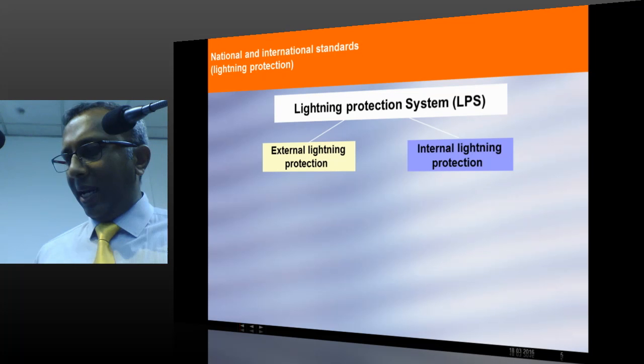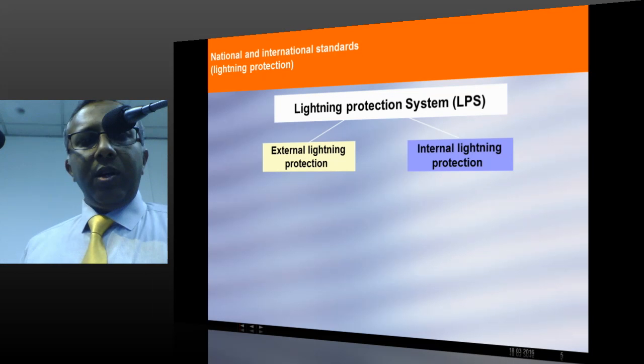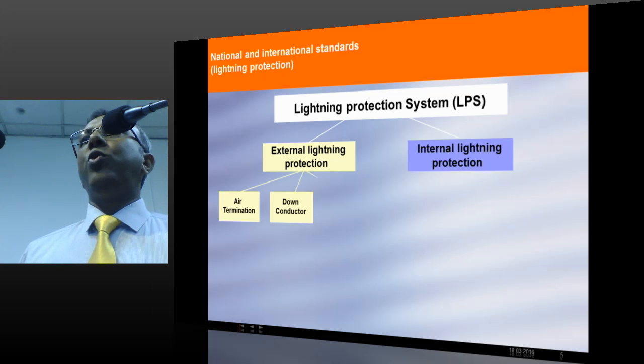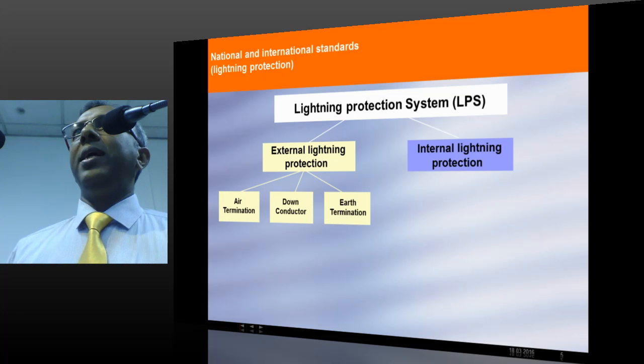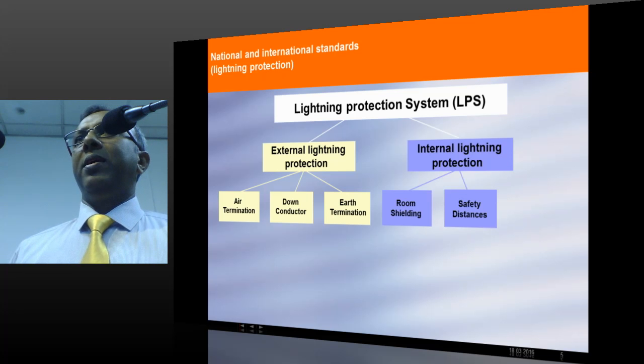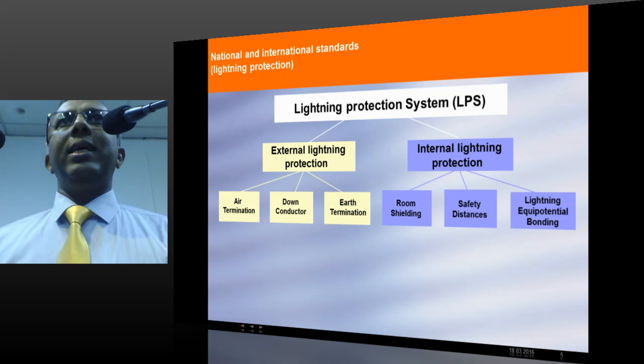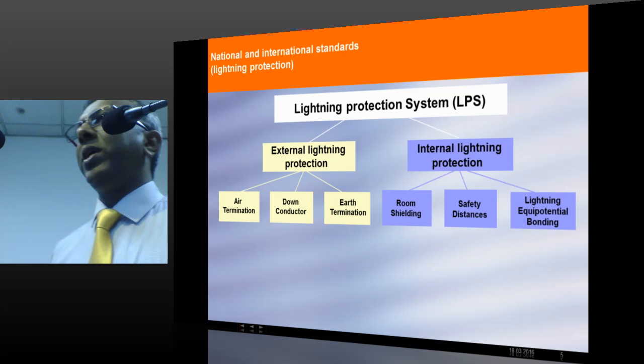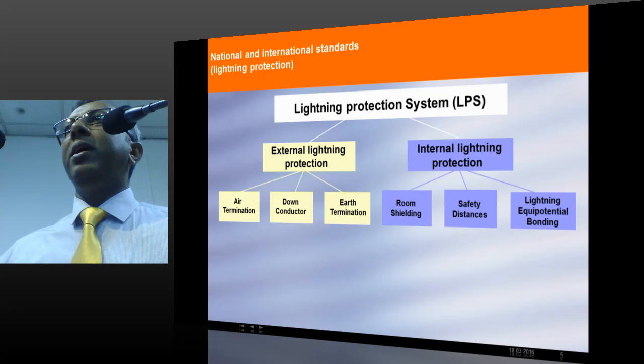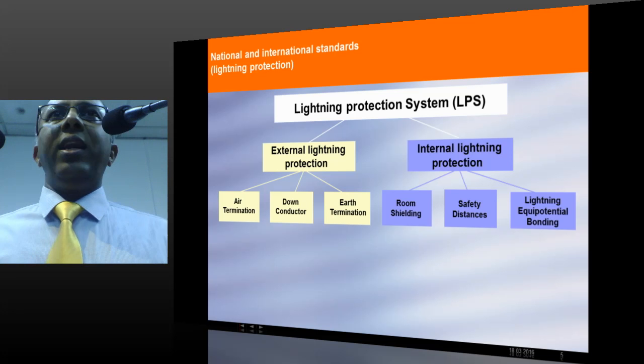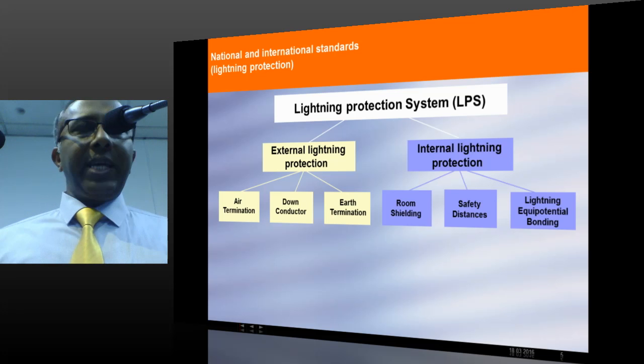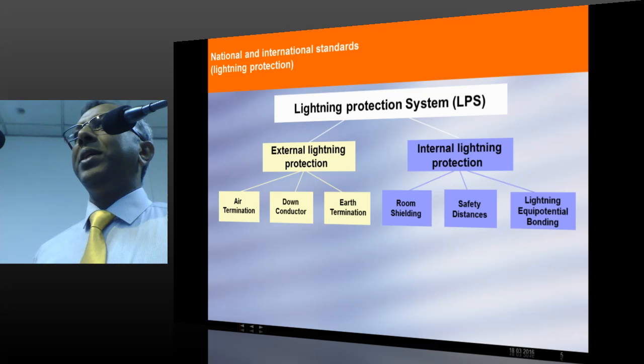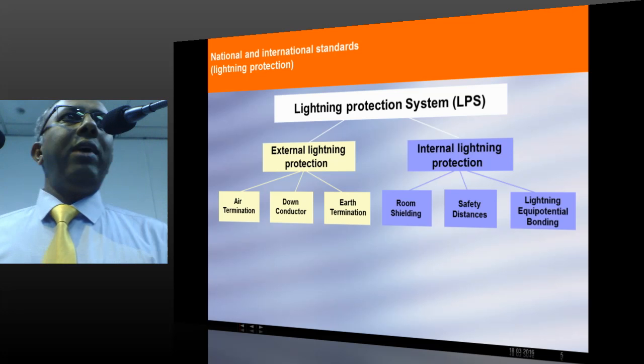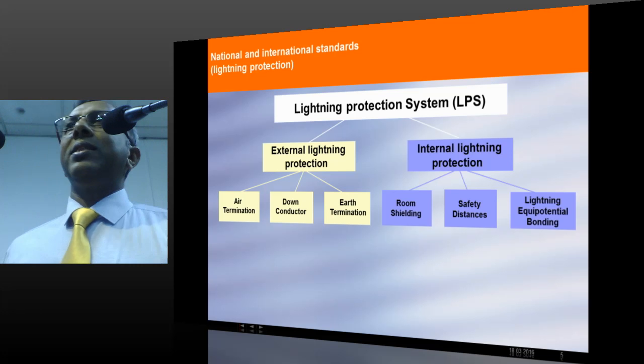Now let me go to the lightning protection standards and lightning protection system. Lightning protection consists of two parts: external lightning protection and internal lightning protection. In external lightning protection, we are talking about protecting a building as well as a structure. And in internal lightning protection, we are talking about protecting human beings and electronic equipment inside a structure. So these two are different subjects. For the first subject, external protection, we need air termination, down conductor and earthing. For the second subject, we have to have room shielding, safety distances and lightning equipotential bonding.